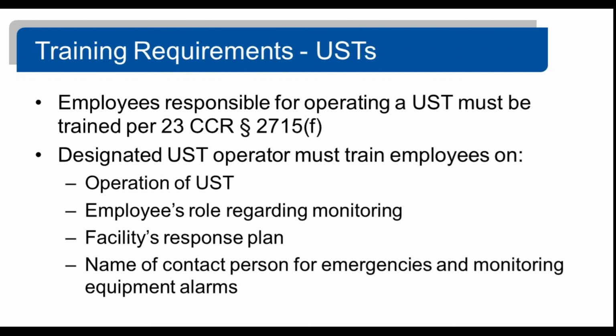These employees also must be trained on the facility's response plan. So if there is a failure to the UST system, an alarm sounds, what the facility's response procedures are, in their specific role as part of responding to a failure alarm for their UST system. Employees also must be trained on the name of the contact person or persons for emergencies and then monitoring the equipment alarms.